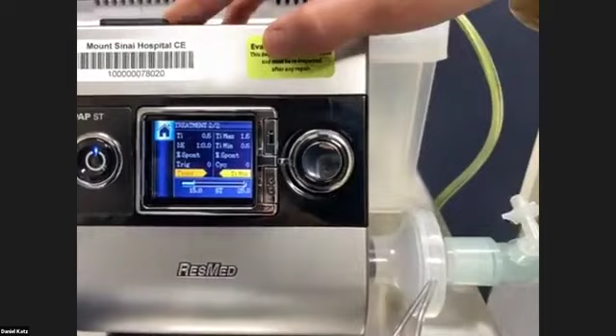In the bi-level ST mode, we will be able to set a mandated backup respiratory rate. The patient can breathe above this rate. Other parameters that can also be adjusted include the inspiratory time limits, which will be determined by the patient's set respiratory rate, as well as rise time, which is the time in which this device takes to reach the goal IPAP. And finally, the sensitivity triggers for breath cycling and triggering. Once patients are connected to this device, we do have a set of clinical protocols that will guide changes needed based on the patient's goal oxygenation and ventilation.